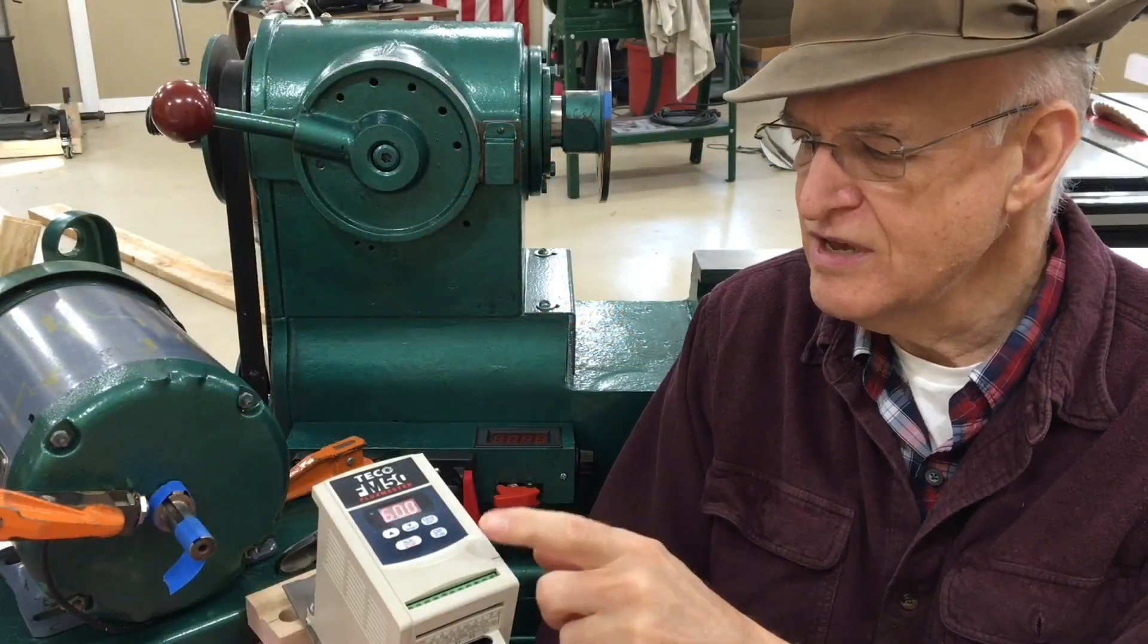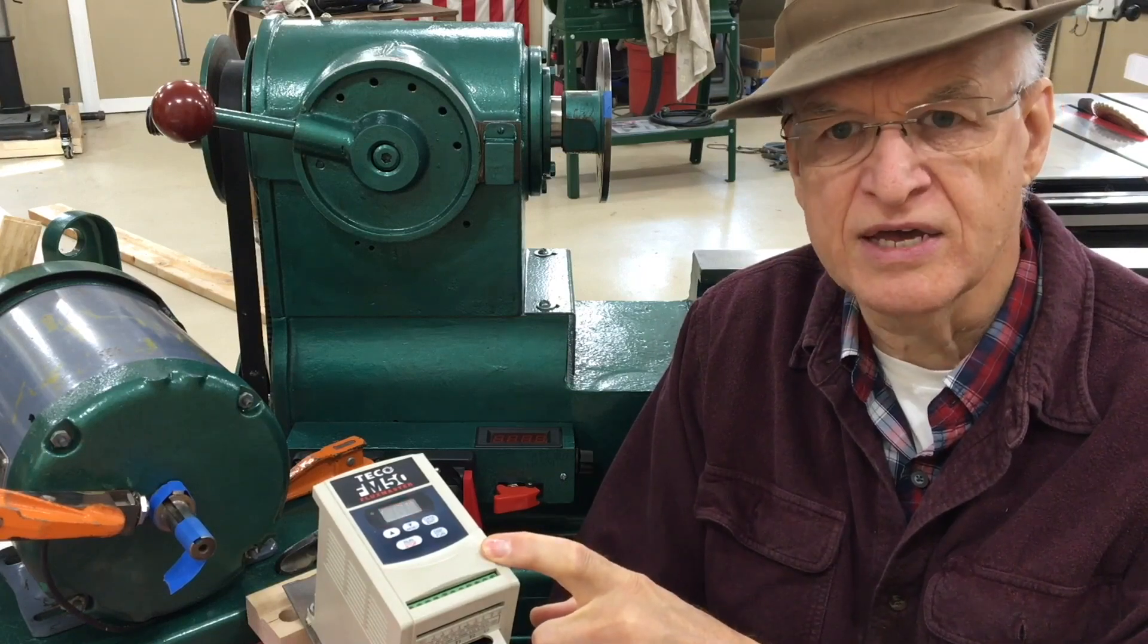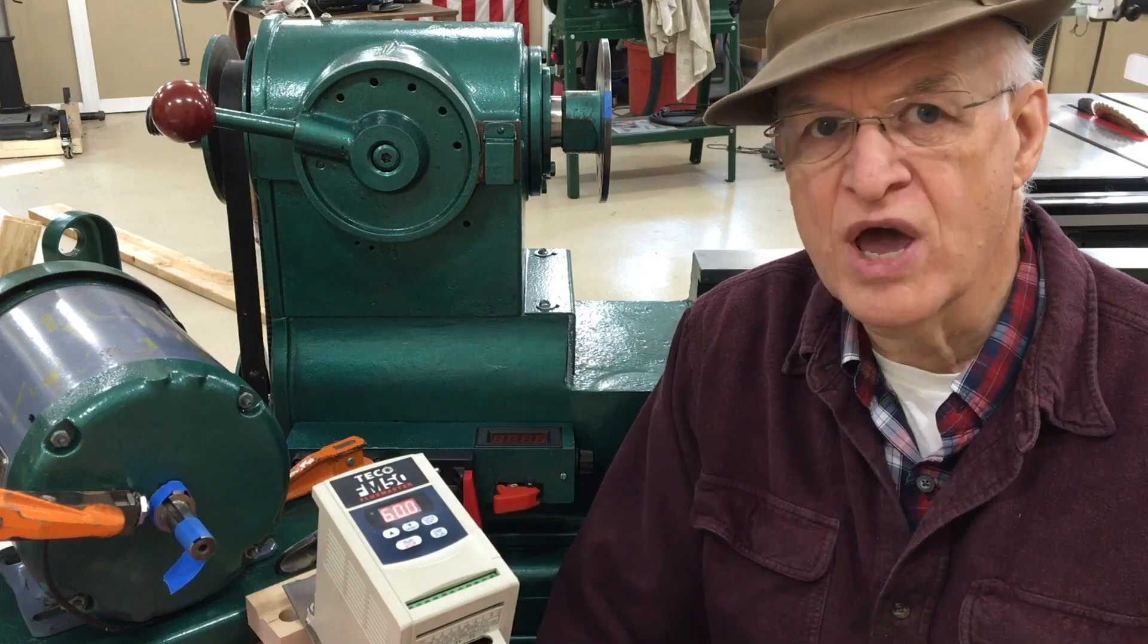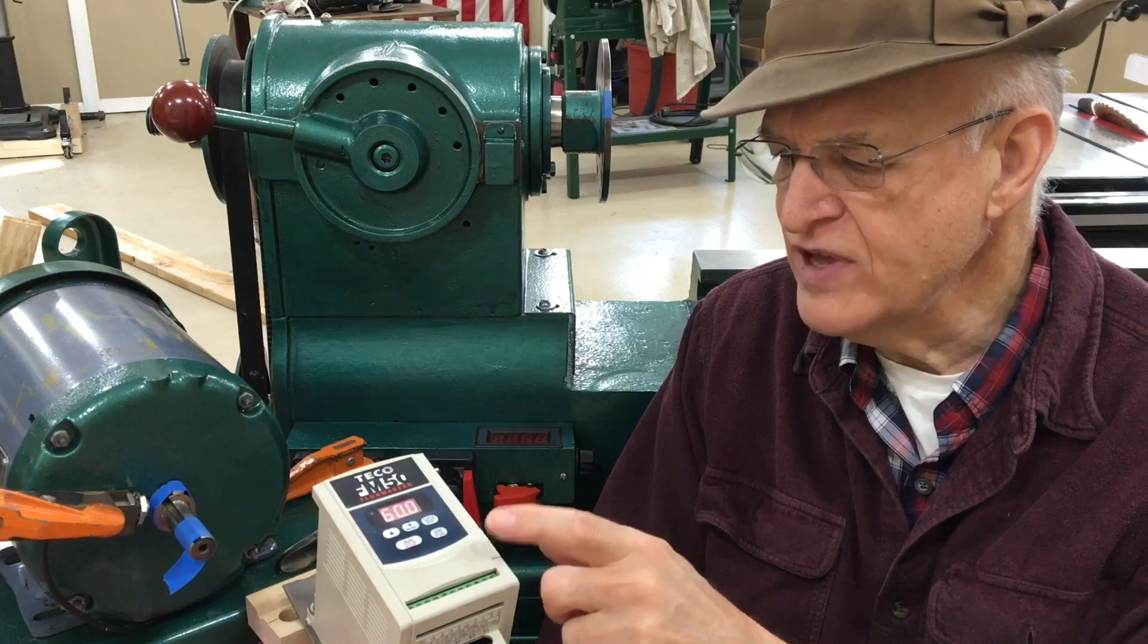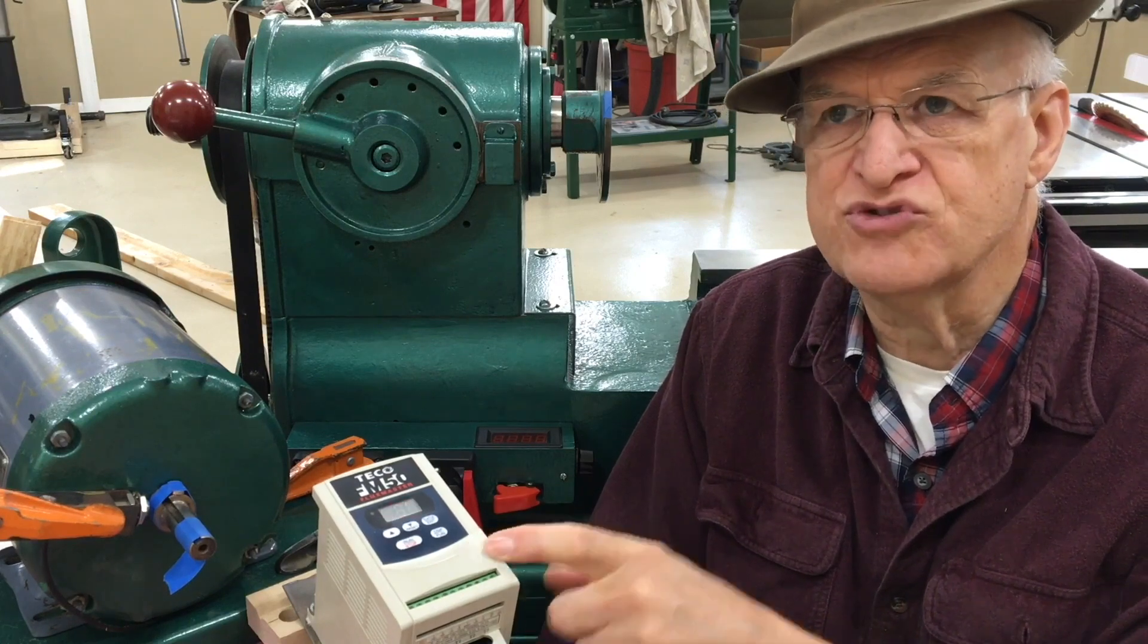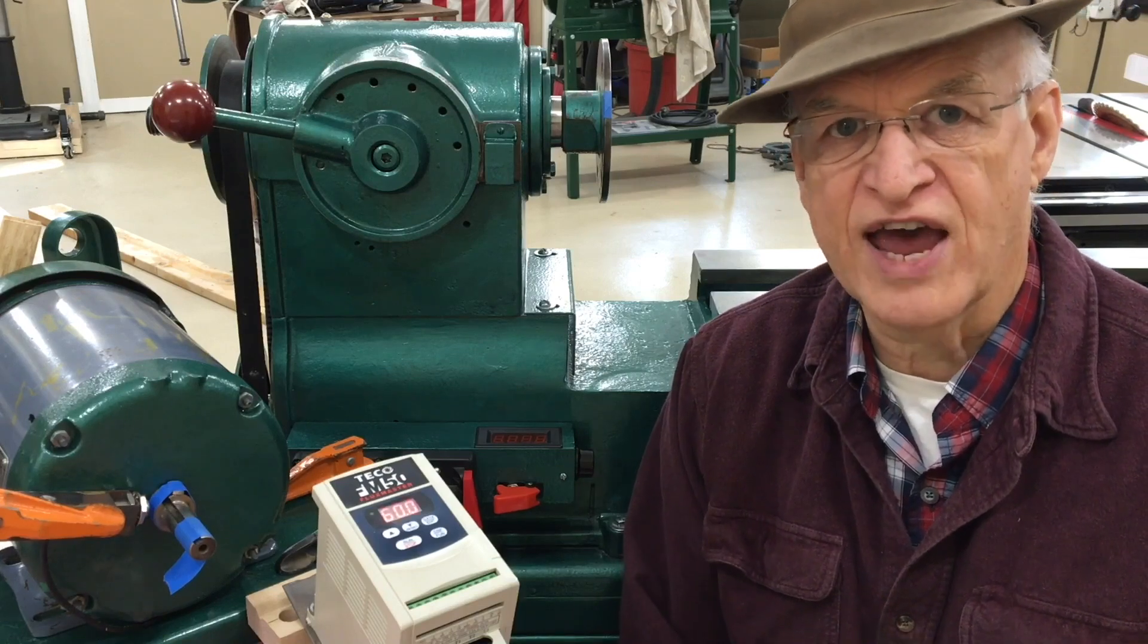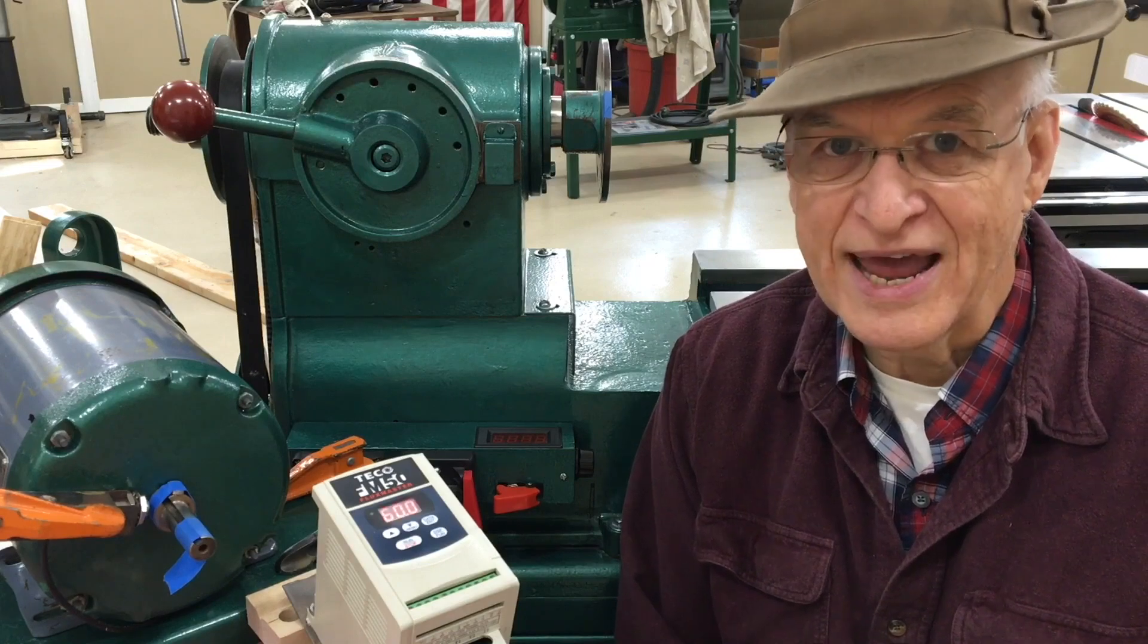This variable frequency drive can vary the frequency between zero and 200 hertz. Well, this motor is designed to run at 60 hertz, 1800 RPMs. If we were to run this at 200 hertz, it would drive the motor at nearly 6000 RPMs three and a half times faster than it's designed to go. And I don't know if I want to see what might happen.